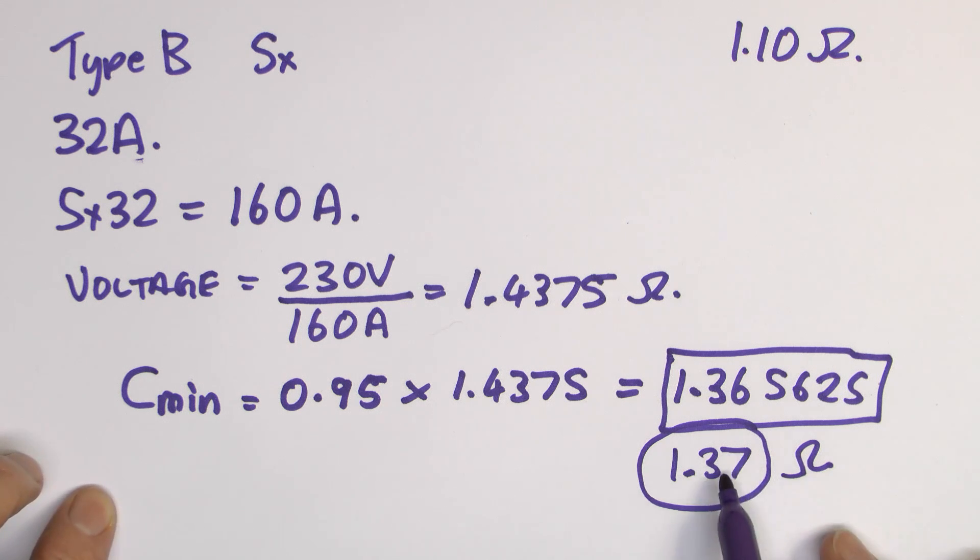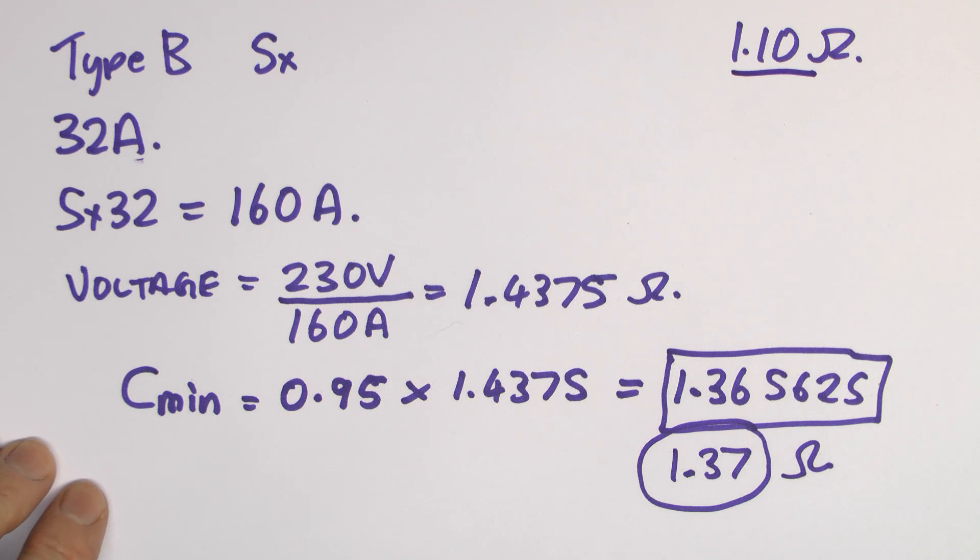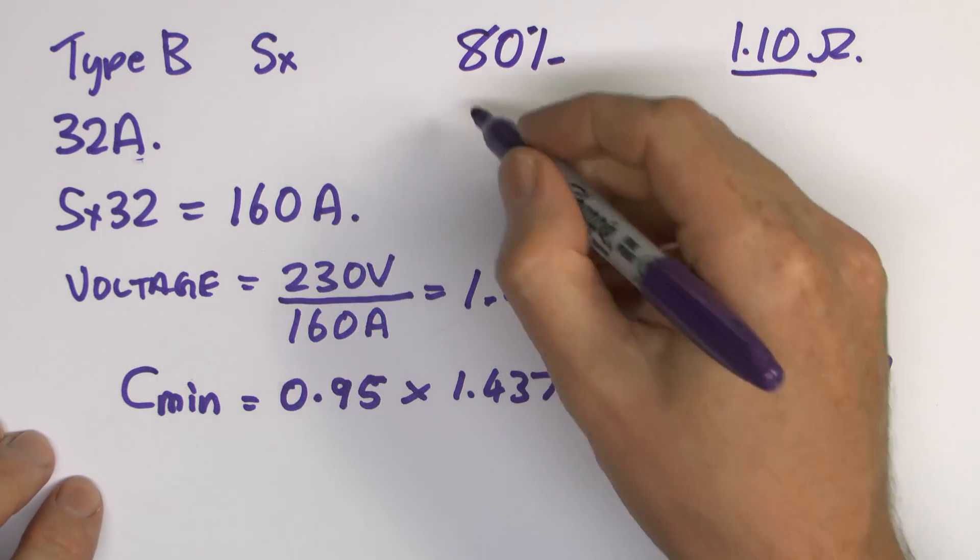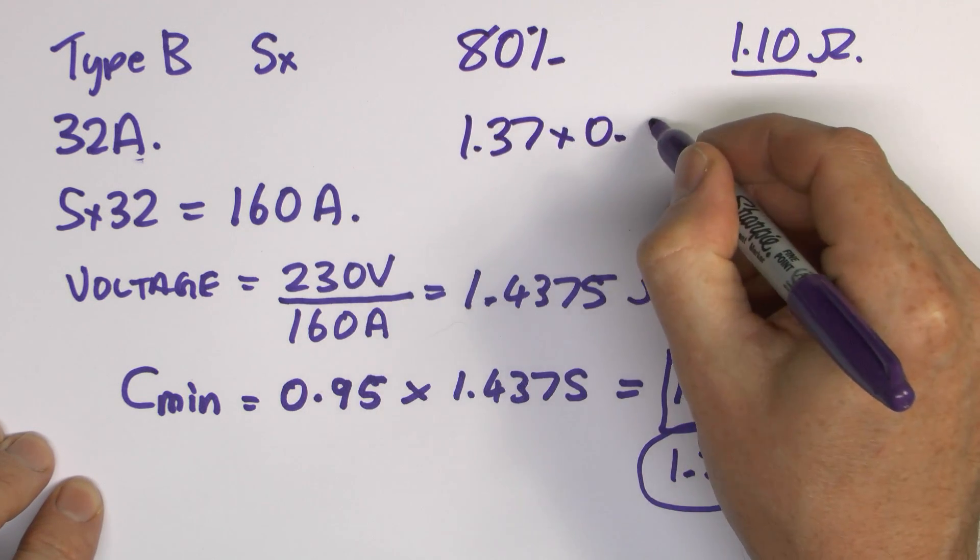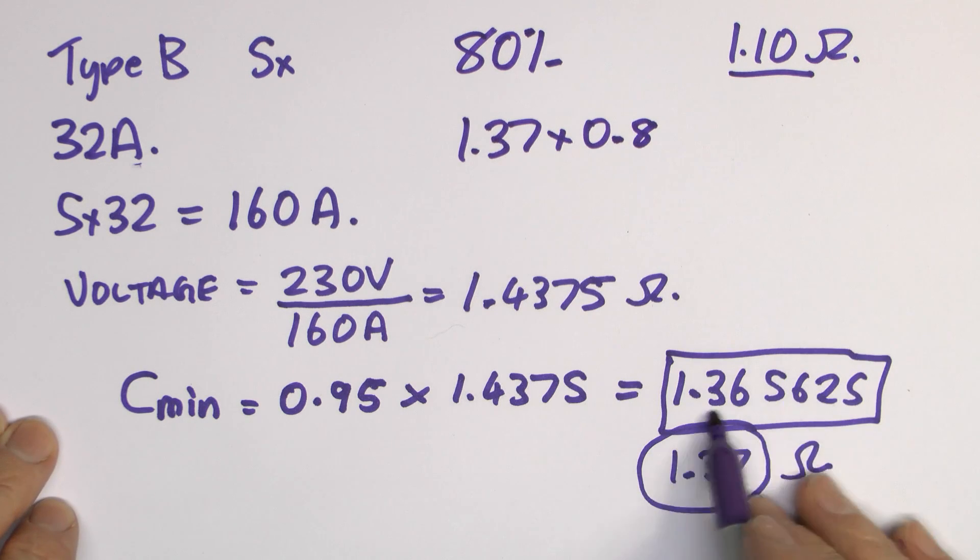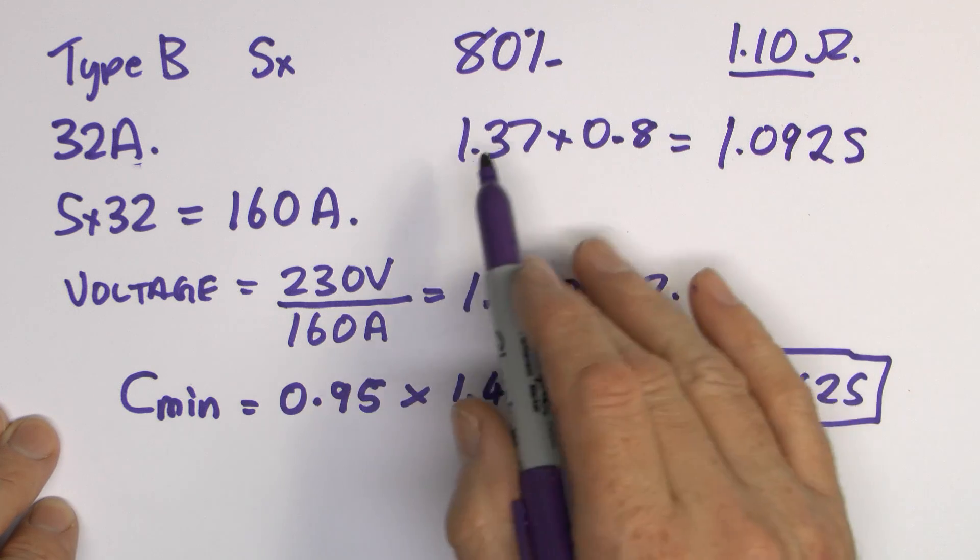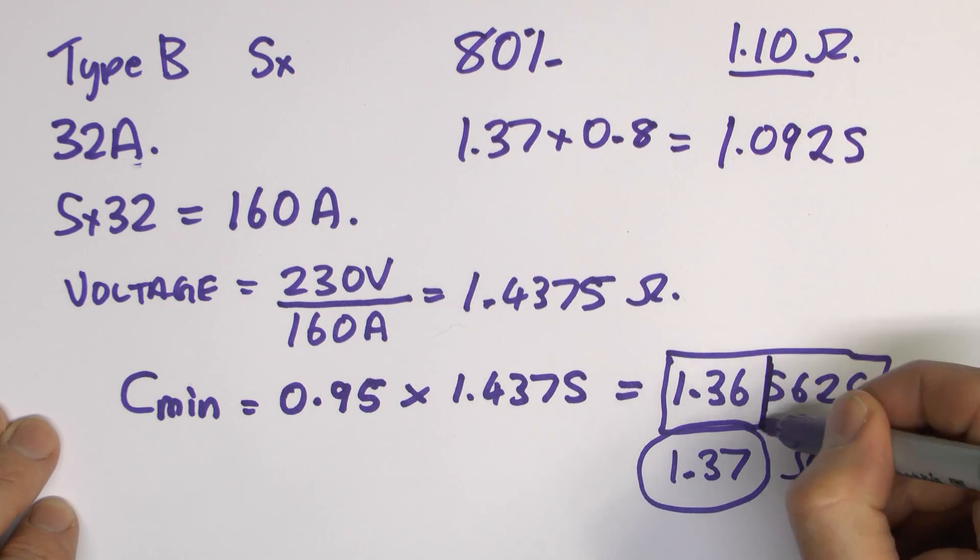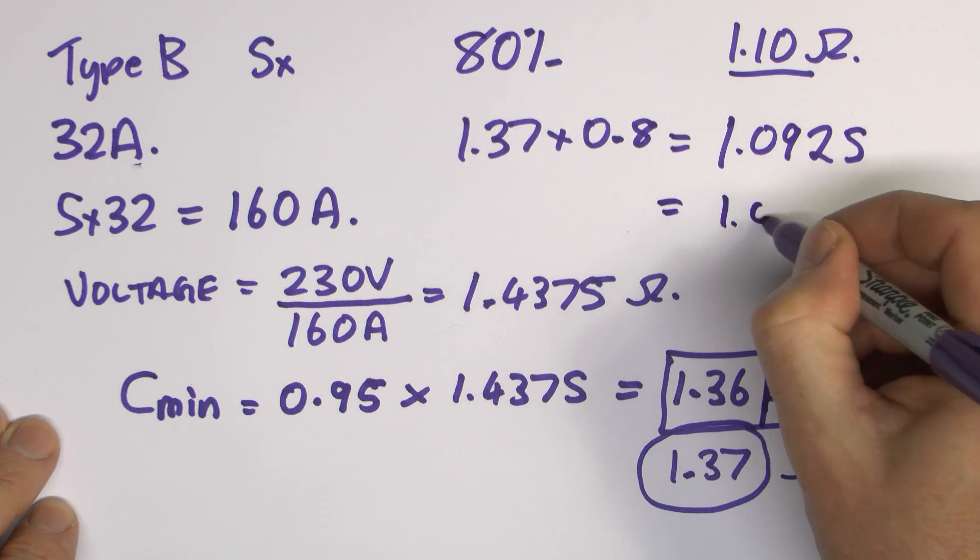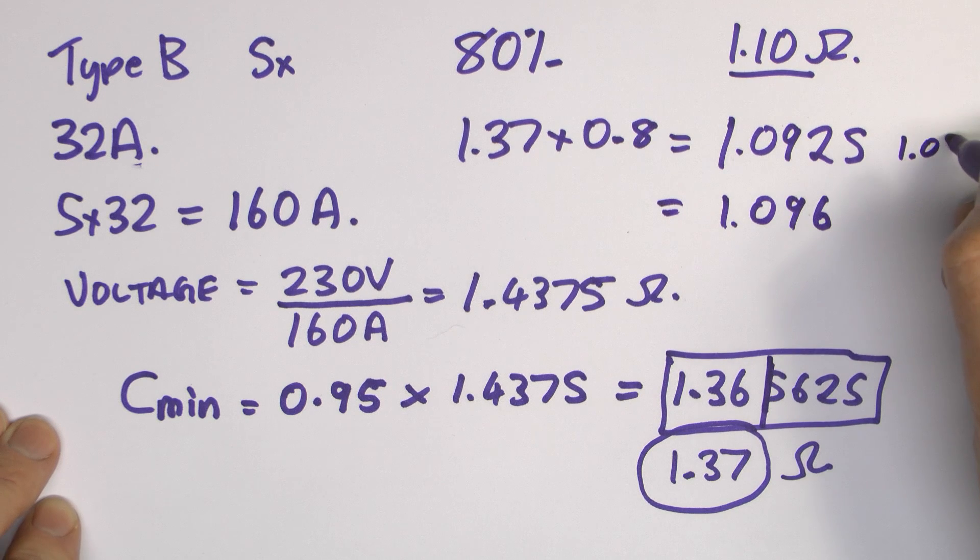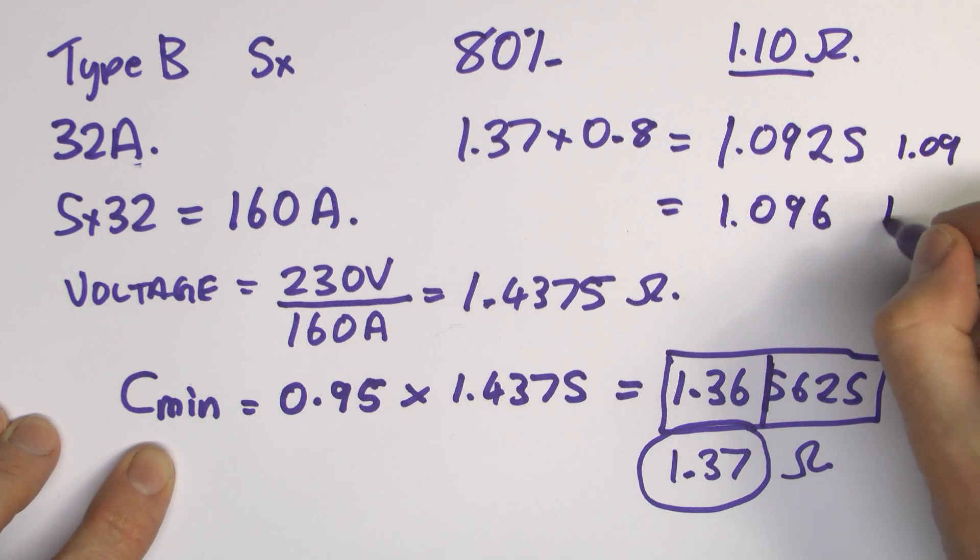Now of course there is another part to this because 1.37 is not 1.10 fairly obviously. However, 1.37 is what's in the BS7671. 1.10 is what's on that printed sheet. And the difference here is 80%. Because what's actually happened is that the 1.37 is being multiplied by 80% or 0.8 effectively. And if we use the full value there with all the decimal places, that actually gives us a value of 1.0925. If we just use 1.37 times 0.8, so basically rounding off at that point already, then the value we get is actually 1.096. So if you're going to round this off to a sensible number of digits, which is basically two decimal places, it's either going to be 1.09, or in the case of this one, if you've rounded it and rounded it again, you get 1.10.